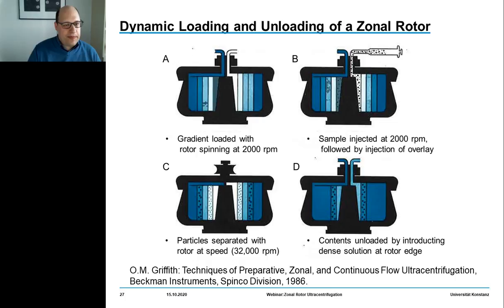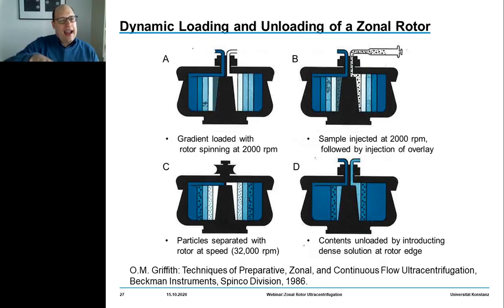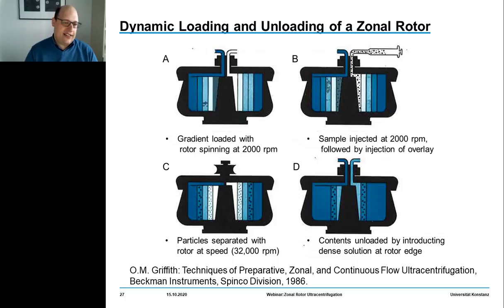Now let's explain how dynamic loading is performed. We start by spinning the rotor at a reduced rate of about 2000 RPM, then begin pumping in the lightest part of the gradient to be built within the rotor chamber. This portion of fluid is pumped towards the edge of the rotor, and this fluid layer will be displaced by layers of next higher densities until the gradient is fully loaded.